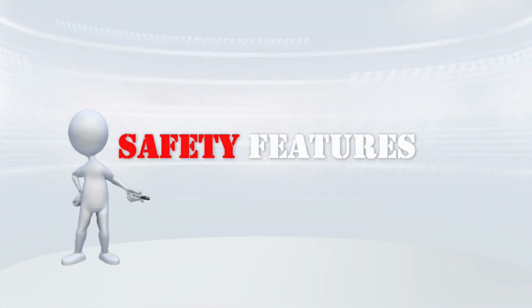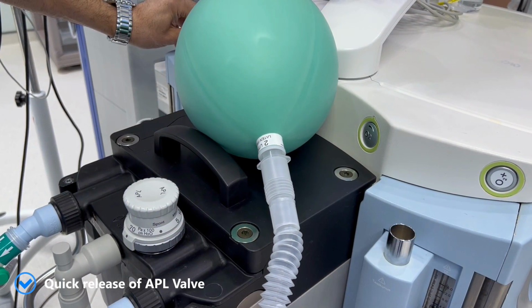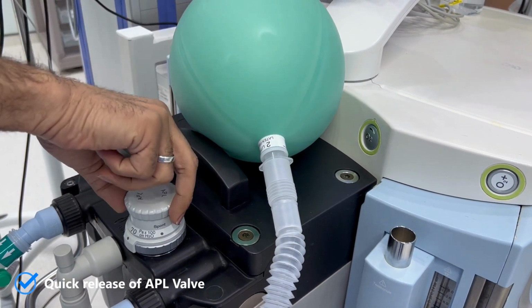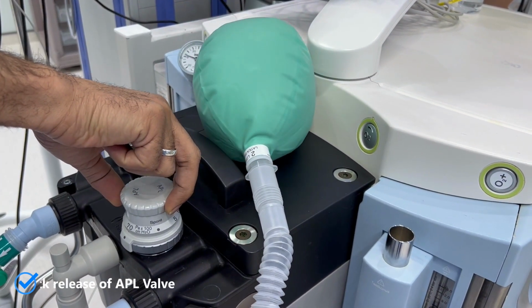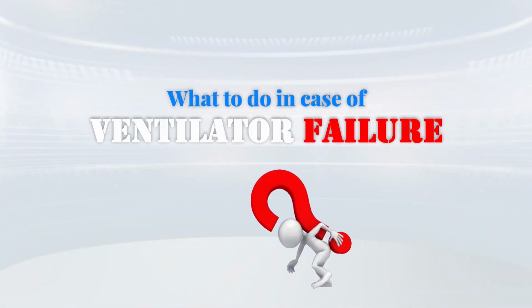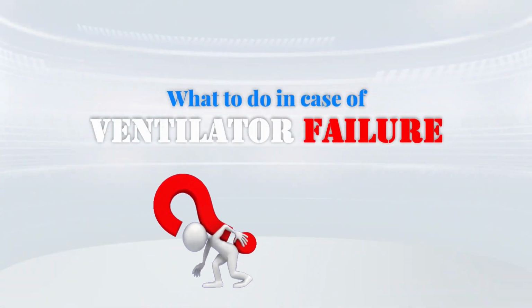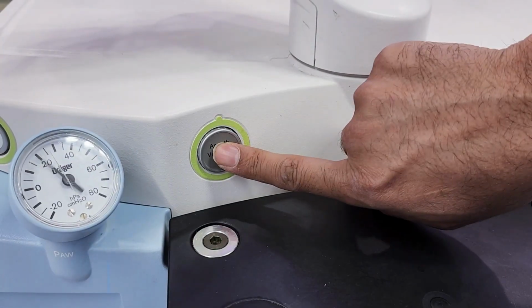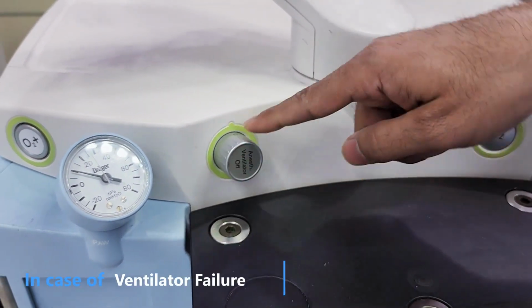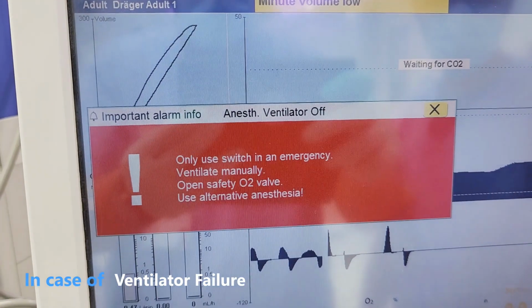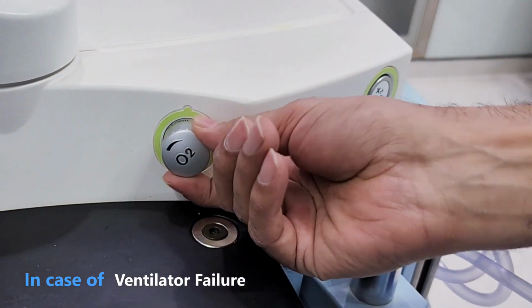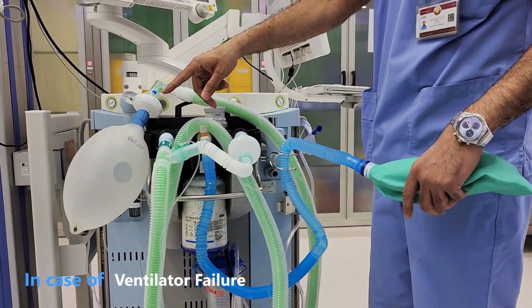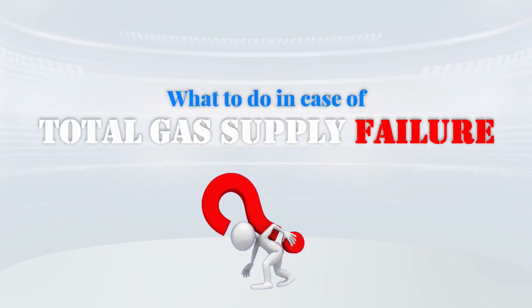Safety feature. One of the safety features of this machine is the quick release of the APL valve. Just pull up for quick pressure release, in case ventilation has to be cancelled due to internal errors. Push the ventilator off button and rotate it towards you. A red message will show after activation. Activate the emergency oxygen delivery system and ventilate the patient manually.